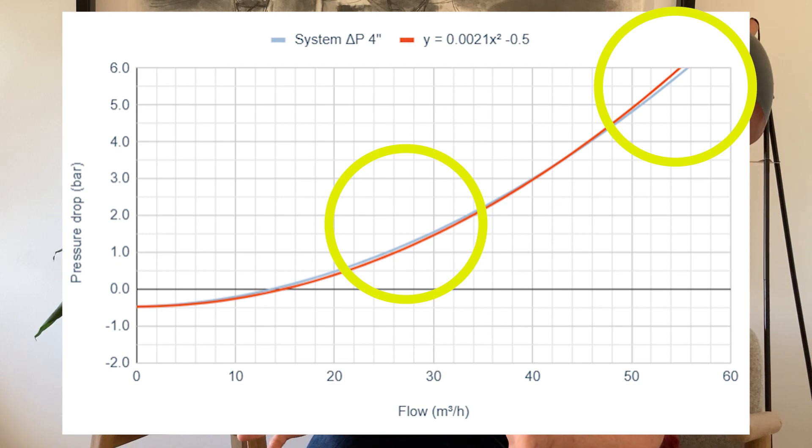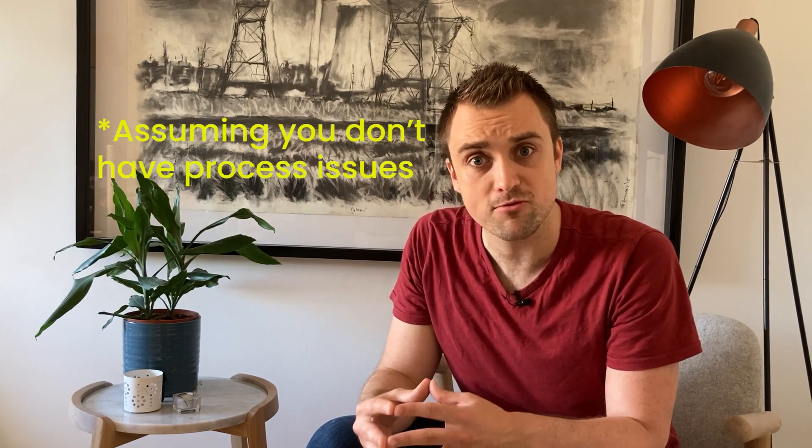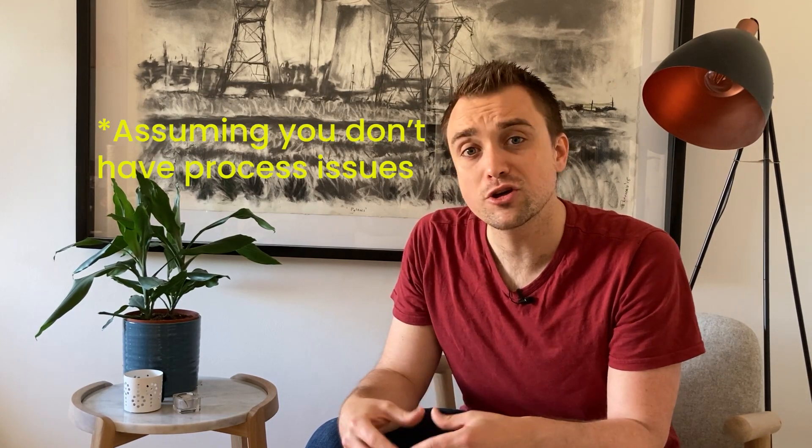A pipeline is fairly simple though. The more complicated the equipment, the more that square relationship will likely deviate and it might not be square at all - it might be some other exponent. The best thing you can do if you have plant data is plot that pressure drop against flow and see what the relationship should be. You can fit the curve to that data and use that as the normalization, so that you're not just looking at pressure drop as a single number.